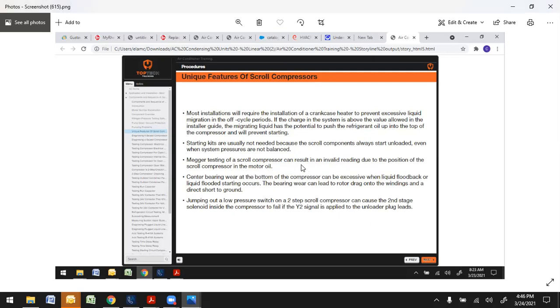So you could take 50 brand new scroll compressors, and if you meg them, they're almost always going to read bad because it's giving you a false reading. Center bearing wear at the bottom of the compressor can be excessive when liquid floodback or liquid flooding occurs. The bearing wear can lead to rotor drag on the windings or a direct short to ground.